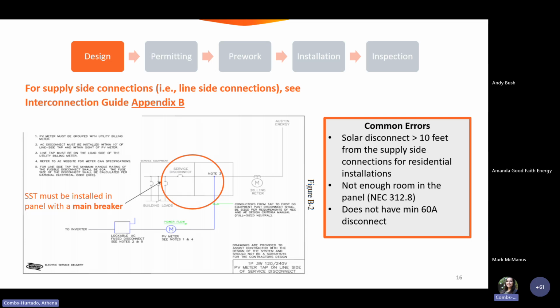All right, so for supply side connections, please make sure that you're seeing the interconnection guide, Appendix B. Some of the common errors we see is that the solar disconnect is farther than 10 feet from the supply side connectors for residential installations. There's not enough room in the panel, and it doesn't have a minimum of 60 amp disconnects. SST must be installed in a panel with a main breaker. Just please make sure that you're looking at the interconnection guide. It has all of the information y'all are going to need.